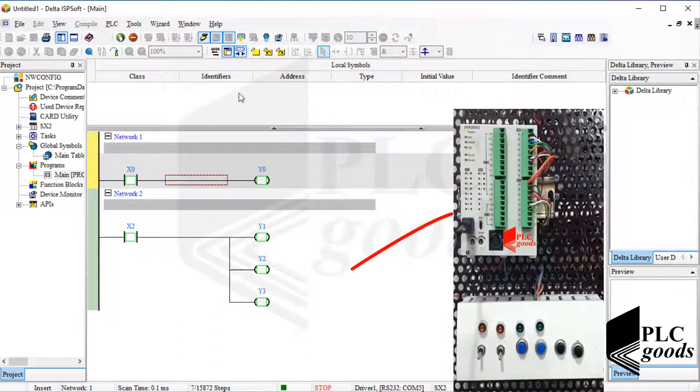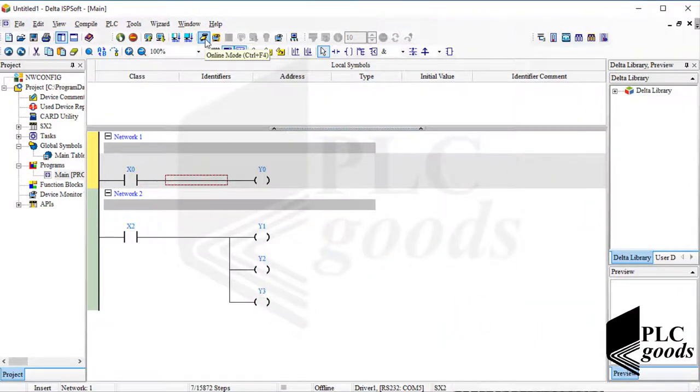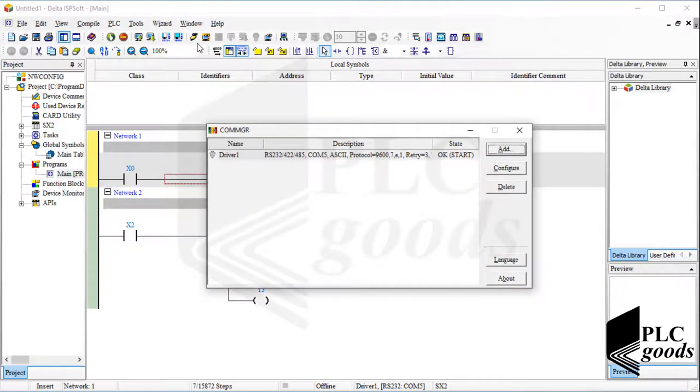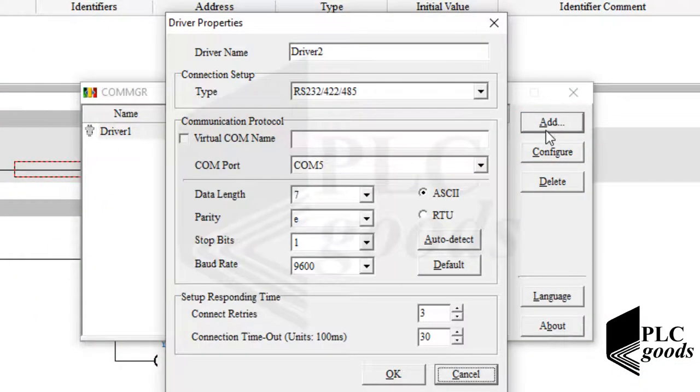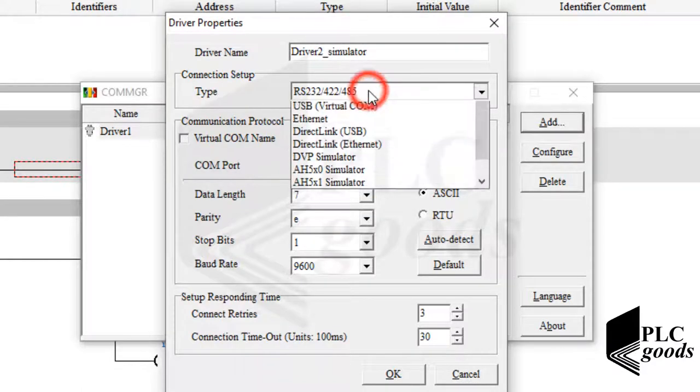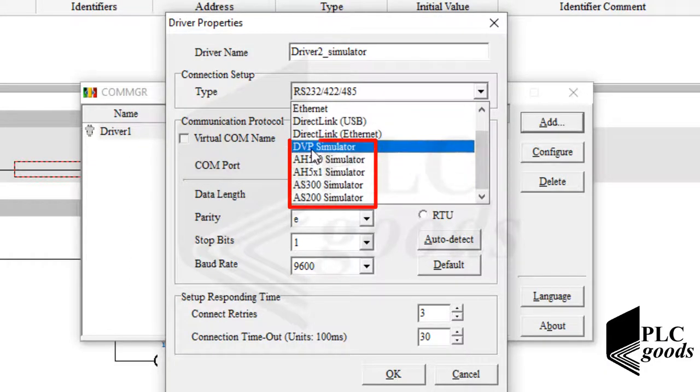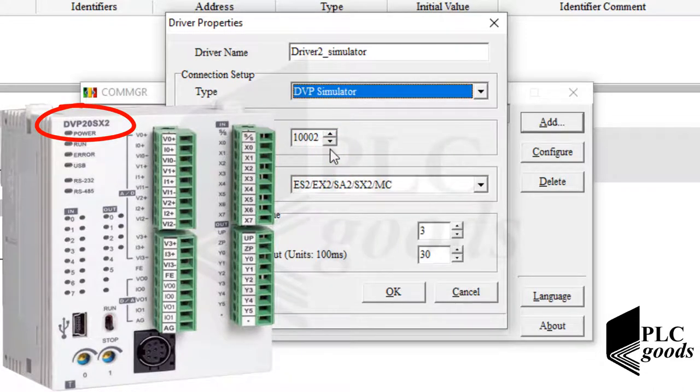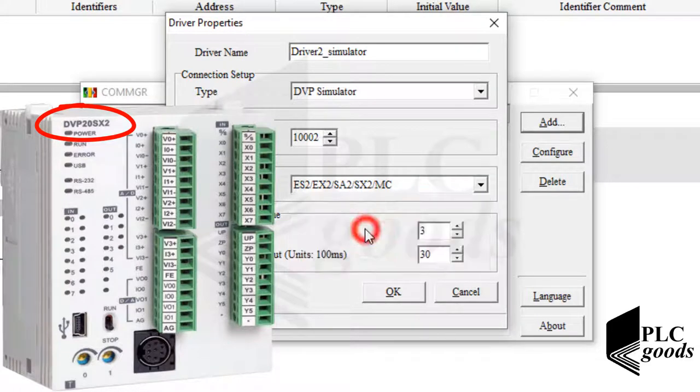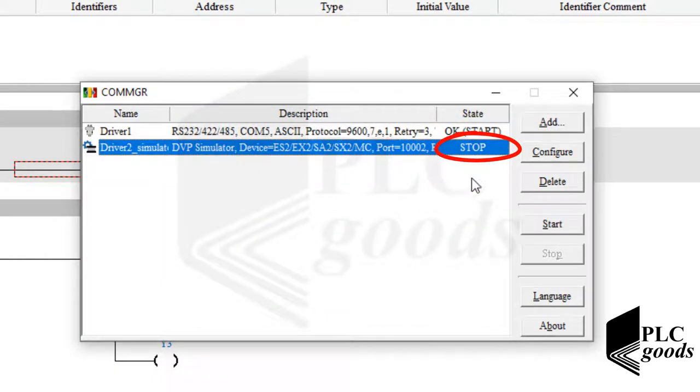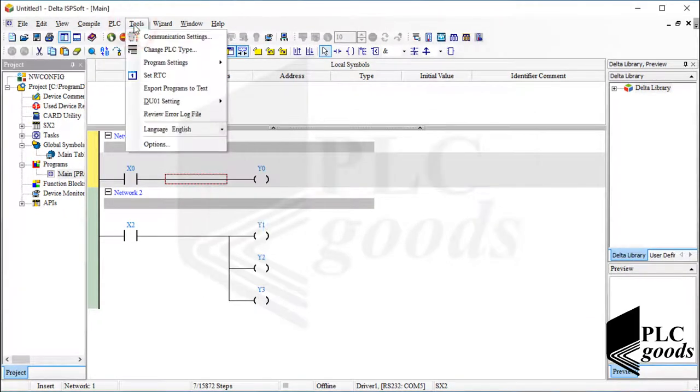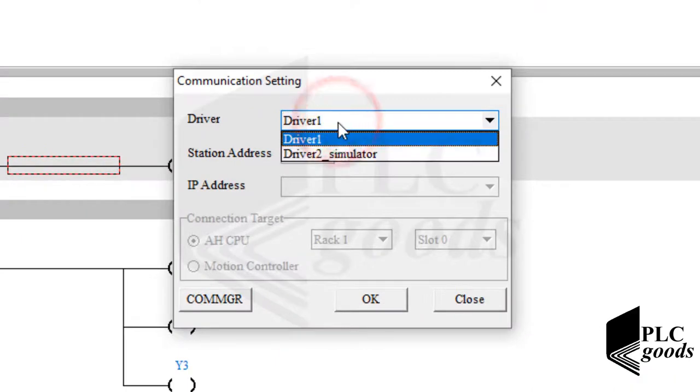Now let me suppose you don't have this PLC. So how you can test this program without this real PLC? First, let's launch COM-MGR software to create a new driver. Let me change the driver name. As you see, under the connection type there are some simulators. Based on the selected PLC type inside the ISPsoft, select an appropriate simulator. I must select the DVP simulator, and after that select this choice under the device menu. Now I must select the new driver and click on start to change its state. Now let's back to ISPsoft, open the communication settings window, and modify the selected driver.